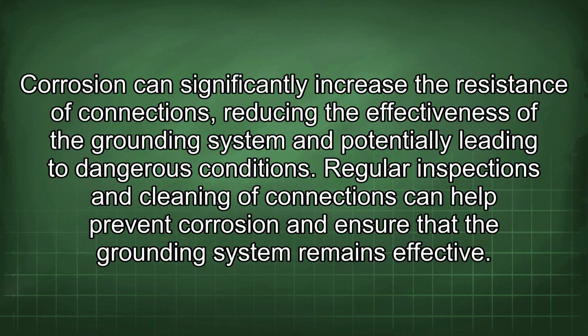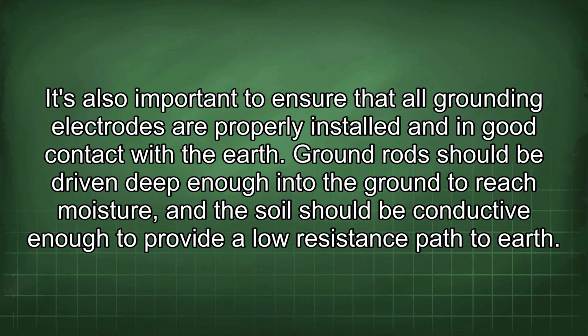Corrosion can significantly increase the resistance of connections, reducing the effectiveness of the grounding system and potentially leading to dangerous conditions. Regular inspections and cleaning of connections can help prevent corrosion and ensure that the grounding system remains effective. It's also important to ensure that all grounding electrodes are properly installed and in good contact with the earth.